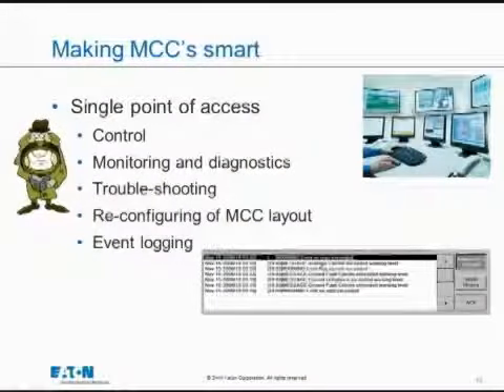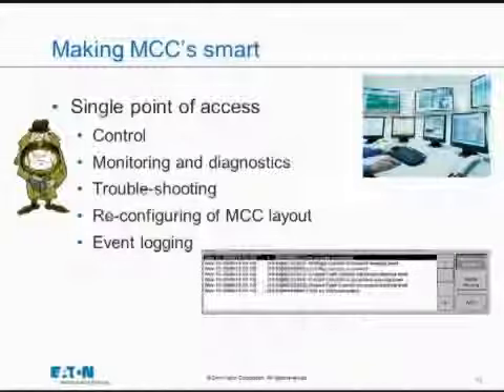So what makes MCC smart? Well, MCCs provide a single point of connection to the upstream system or the SCADA system. What that does is basically allow you to have predefined mapping tables, which means that when you get a smart MCC or an intelligent MCC, you're already getting a mapping table that says how to communicate with this, and that mapping table is usually standard. So regardless of the motor control center that you're getting, how large it is, what's inside each cell, the mapping table usually stays the same, which means that when the MCC arrives on site, the information is available at time of order, so the programmer who's doing the SCADA system can actually interface to it and even test it at the factory without ever waiting for it to arrive in the field. Consequently, that minimizes a lot of problems that you would have.